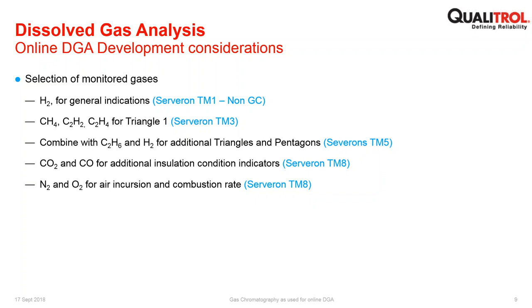So usually it's a single gas, solid state sensor type system, and Serveron have one of those called TM1, but it's not GC. Then for gas chromatography applications, or for multi-gas applications, you would perhaps look at methane, acetylene, and ethylene, which would give you Duval's triangle number 1. If you add in or combine ethane and hydrogen, you get the other Duval triangles, and you also get to use the Duval pentagon for diagnostics. Add in CO2 and carbon monoxide for additional insulation information. So this is in relation to the breakdown of the paper insulation. And then, of course, the atmospheric gases, nitrogen and oxygen. The Serveron products and gas chromatography products in general can measure all of these gases on a single detector, with reference to a recent calibration.